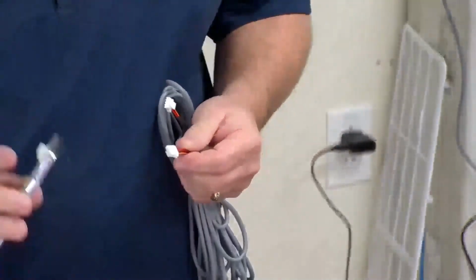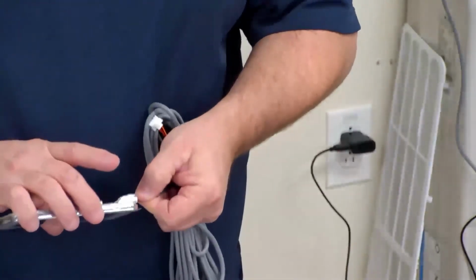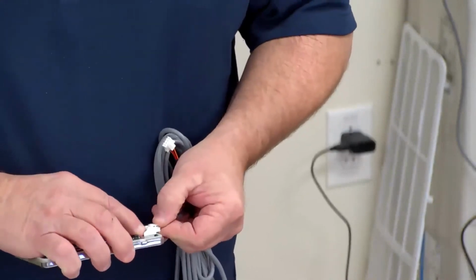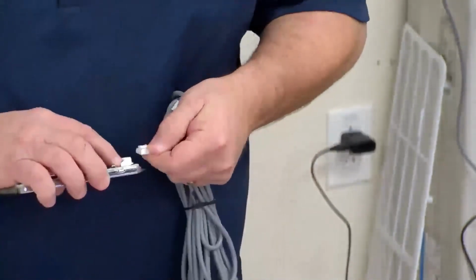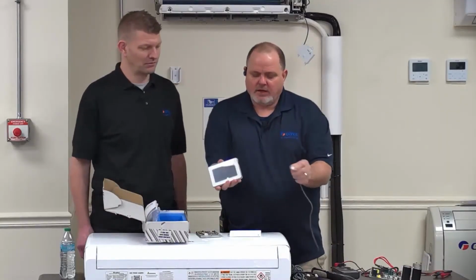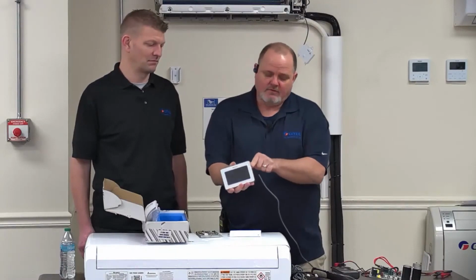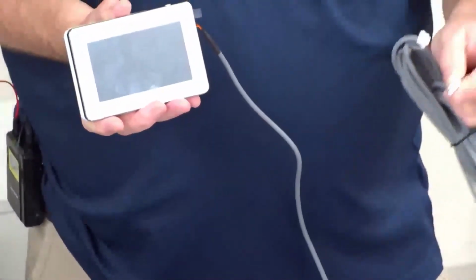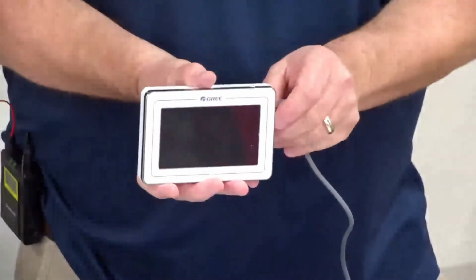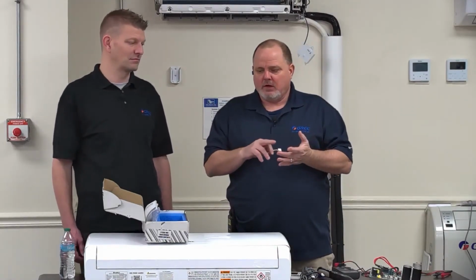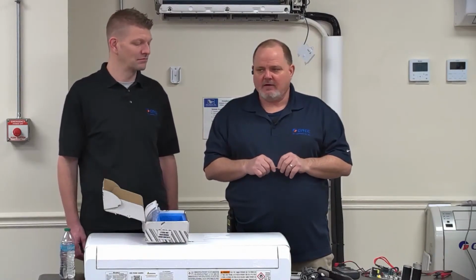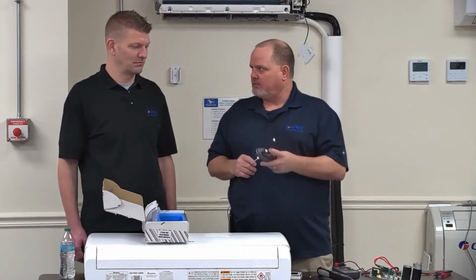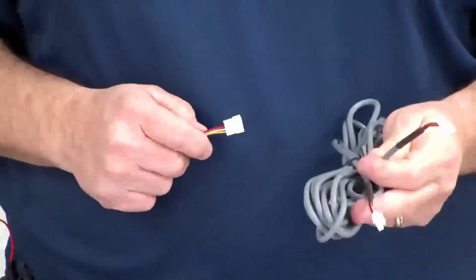So when you go to plug it into the service tool that's all together, it'll clip in there. What I've found is that if you have that plugged in, you can unplug it and plug it back up. But if you leave that keeper in there, it keeps you from squeezing that tab to release it, so you really fight getting it to unplug. That's my whole point there. So make sure you're getting rid of them gray keepers. Most of the units on MultiPRO, whether it be a cassette, a wall mount, or a ducted unit, have the 4-pin Molex plug on the circuit board in the machine that you can plug up to make the service tool work.